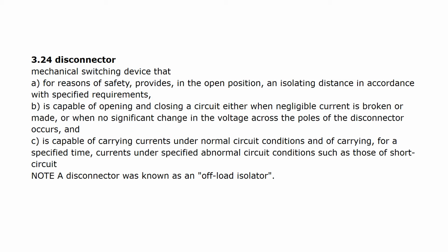Disconnector, mechanical switching device that: A, for reasons of safety, provides in the open position an isolating distance in accordance with specified requirements; B, is capable of opening and closing a circuit either when negligible current is broken or made, or when no significant change in the voltage across the poles of the disconnector occurs; and C, is capable of carrying currents under normal circuit conditions and of carrying for a specified time currents under specified abnormal conditions such as those of short circuit. Note, a disconnector was known as an off-load isolator.